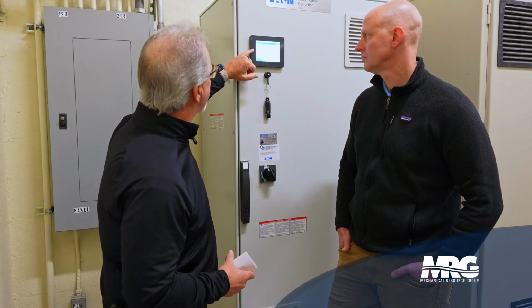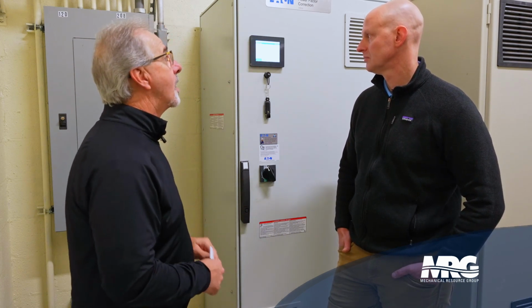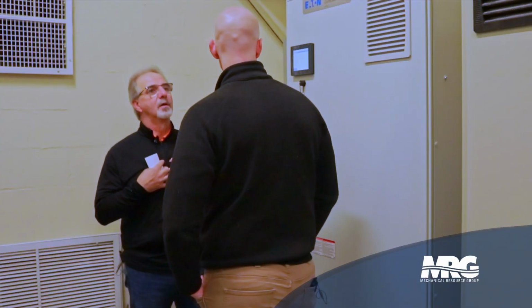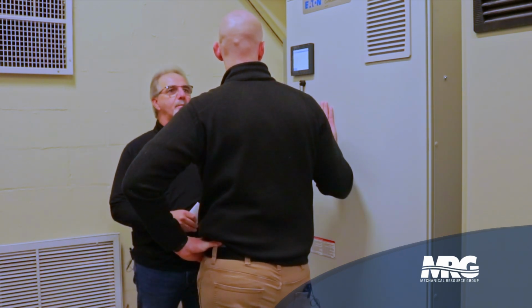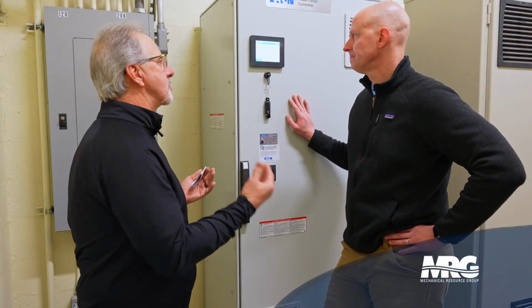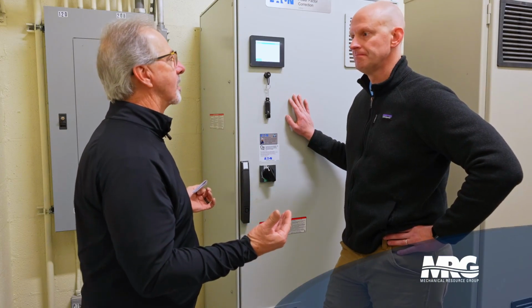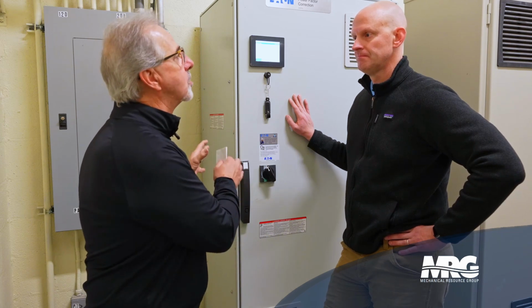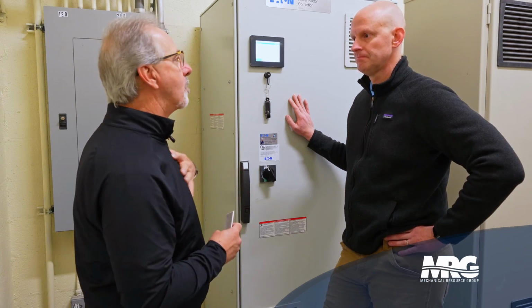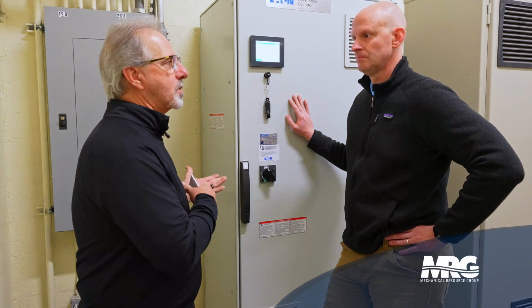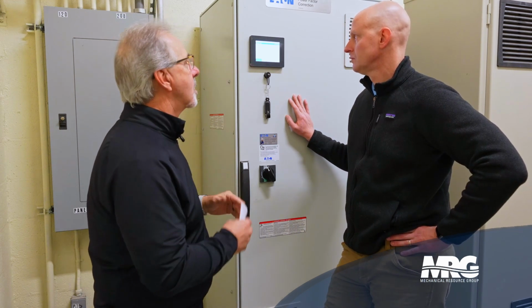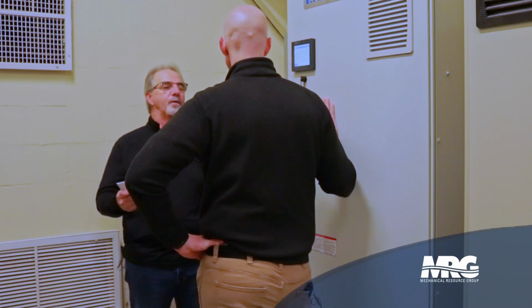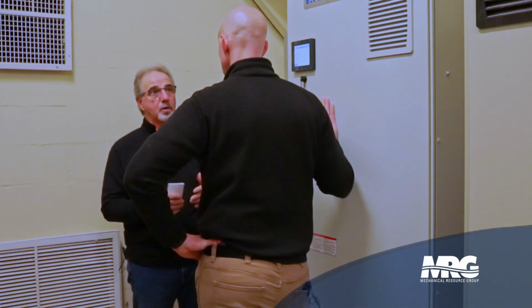But if you'll notice, the second line down that says load harmonics, that's how many amps of polluted waveform we're having to correct. So it tells you what you've got coming in, and then the next line down tells you how many output harmonics. You'll notice I'm at 0 amps right now in harmonic content. So the active filter, that's how you know it's doing its job. What we wanted to do was get down to about 3% of load harmonics, and we found out when we only run one, we're at 0 amps. We're actually cleaning it back up, almost sinusoidal.